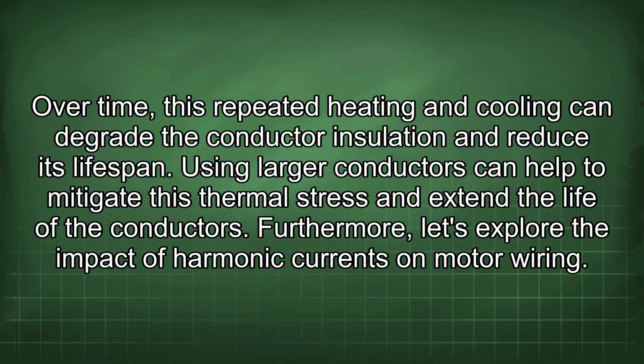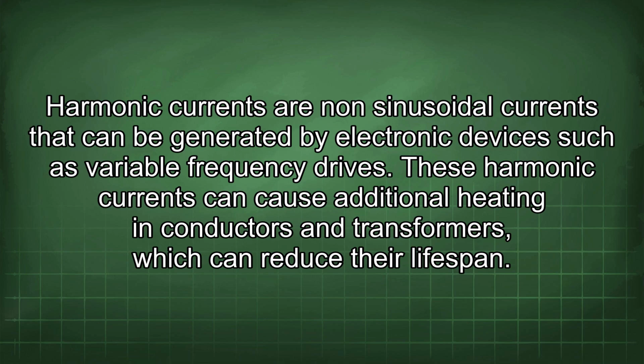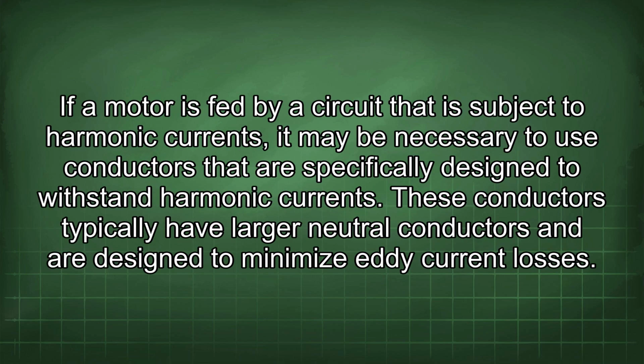Furthermore, let's explore the impact of harmonic currents on motor wiring. Harmonic currents are non-sinusoidal currents that can be generated by electronic devices such as variable frequency drives. These harmonic currents can cause additional heating in conductors and transformers, which can reduce their lifespan. If a motor is fed by a circuit that is subject to harmonic currents, it may be necessary to use conductors that are specifically designed to withstand harmonic currents. These conductors typically have larger neutral conductors and are designed to minimize eddy current losses.